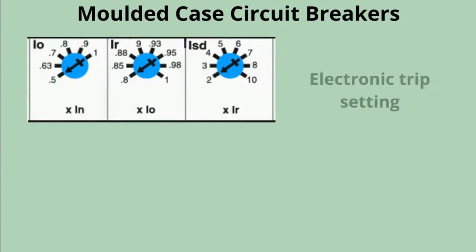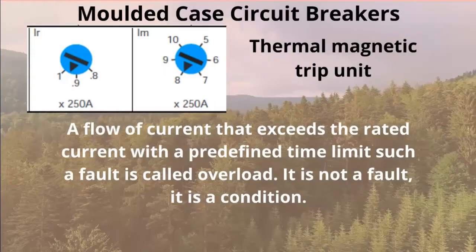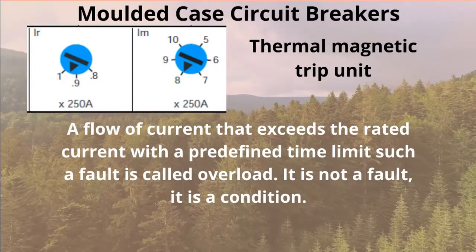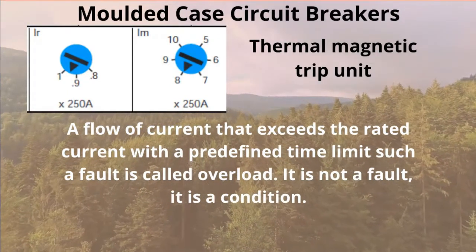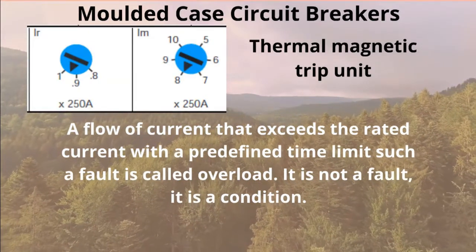Thermal magnetic trip unit and electronic trip unit. For the thermal magnetic trip unit: a flow of current that exceeds the rated current with a predefined time limit — such a condition is called overload. It is not a fault; it is a condition.